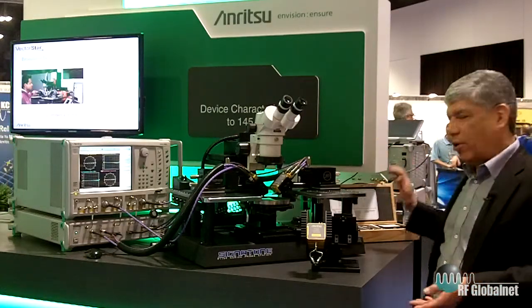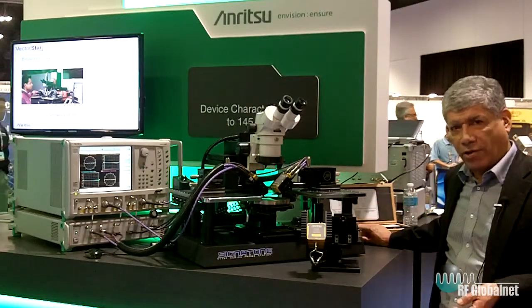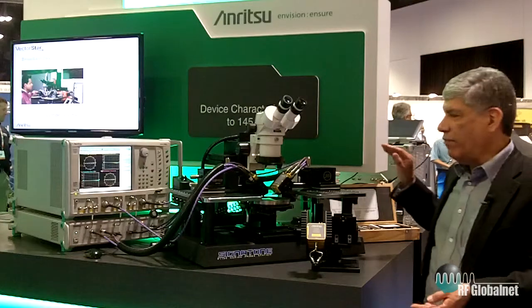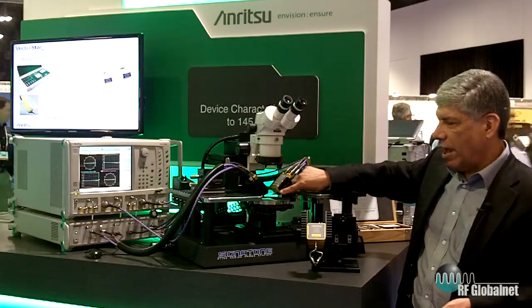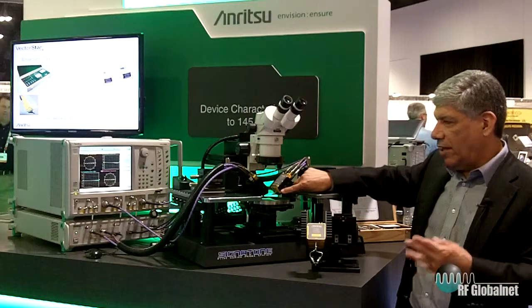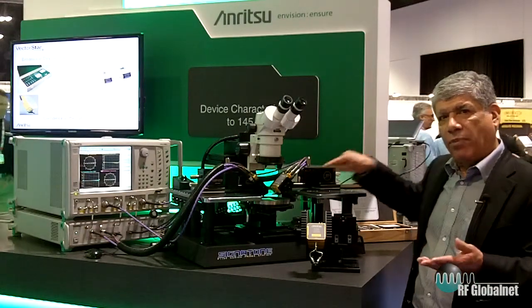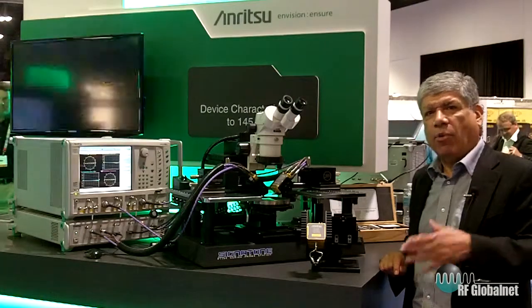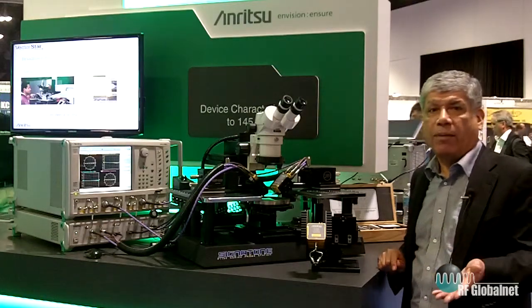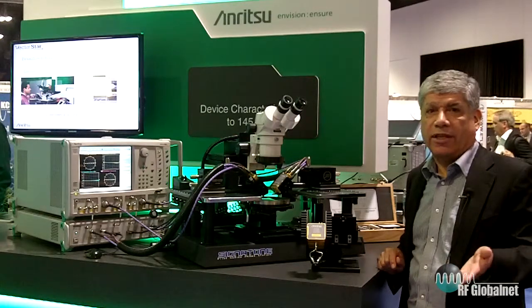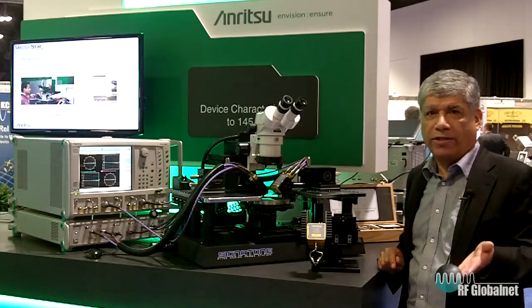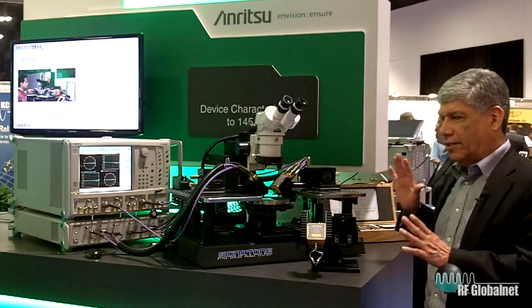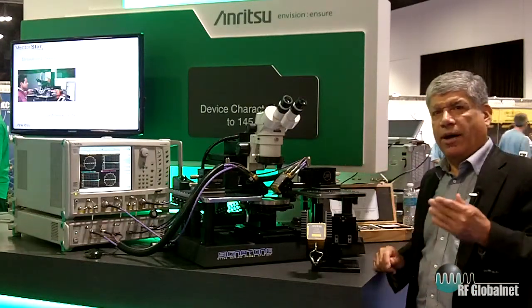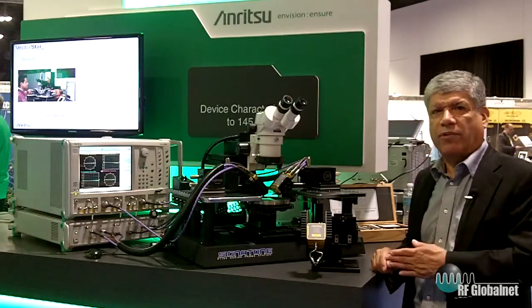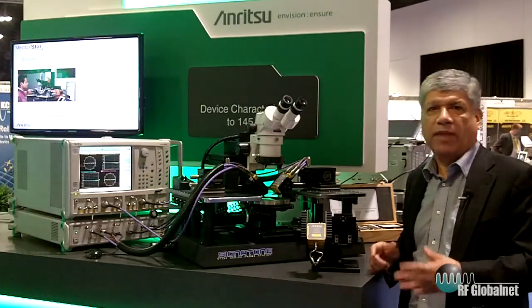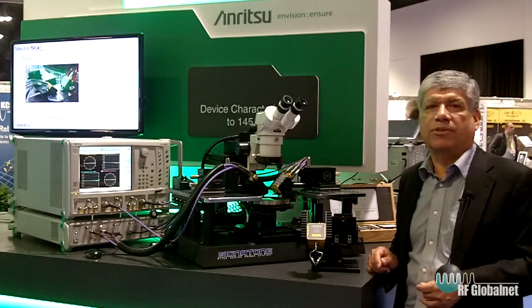And that connector is supported by a coaxial cal kit as well as verification kit. But for on-wafer measurements, we are now connected to a probe that is a GGB with 0.8 connector, and we're able to make measurements all the way to 145 in a broadband configuration. And doing LRM calibrations, we're getting directivities in the range of high 30s to the 40 dB range. So the stability and accuracy are still there. The capability to sweep even to higher frequencies is something we're now providing as a new benefit for the device characterization customers. Thank you.